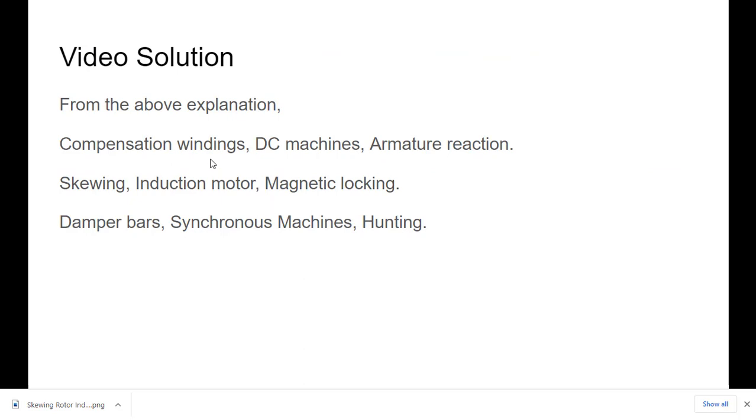From the above explanation, compensating windings are used in DC machines and are used to reduce the cross magnetization effect of the armature. And the skewing of the rotor bars is placed in induction motor and it helps to reduce the magnetic locking. And damper bars are placed in synchronous machine and it helps in hunting to attain the synchronous speed.